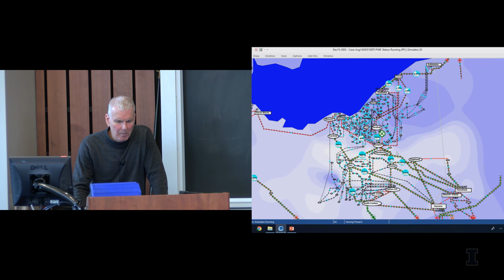It was one that was not heavily loaded. The pie charts there, which are kind of hard to see in the back, are showing the percentage loading on the lines. The line that tripped out first was actually only loaded at 37% of its limit. It opened up because a tree got too close to it, so it arced. The protective relays took out the line, and then they tried to put it back in service, but because the tree was still there, they couldn't. The line went out of service.